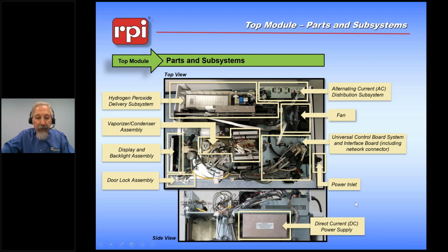So I'm going to turn on a pointer, and we're going to be talking about each of these individual sections. Some of them we're just going to see here. This is where the AC power is brought into the machine and distributed. There is a cooling fan. This box contains all of the CPUs and all of the various I/O cards. We have something called a vaporizer condenser assembly. That's where the hydrogen peroxide is vaporized and then concentrated before we deliver it into the chamber. We have our pressure transducers.